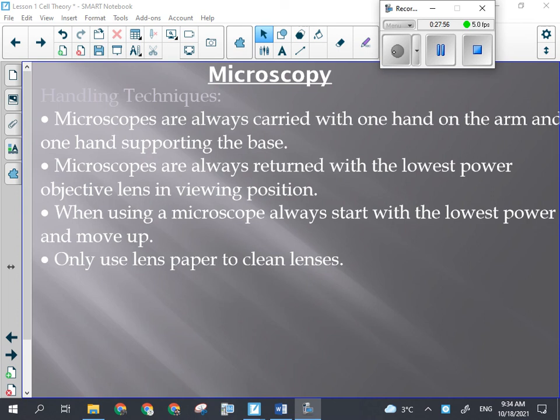And sometimes these brakes get kind of pulled off. Like this one here, it hit the brake before it hit the slide. But some of them are off a little bit. They've slipped or whatever, and you can actually drive the microscope lens right into the slide, which will damage both of them. And that's a really expensive repair that I can't do. So we need to make sure we're careful about using that.